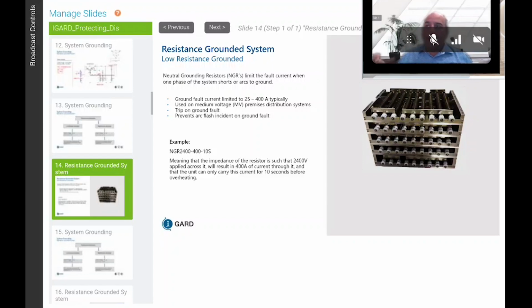So what is the minimum pickup of your ground fault protection in your system? If your minimum pickup of a ground fault is 50 amps, then certainly you can pick a 100 amp, 200 amp ground fault current on your resistor. If your minimum pickup is going to be 400 amps, you can't detect a fault of less than 400 amps, so it has to be greater than 400 amps. So your protection system dictates what size the resistor should be.